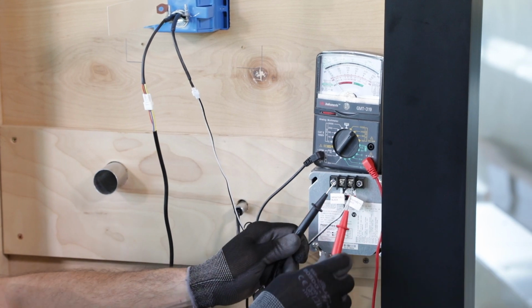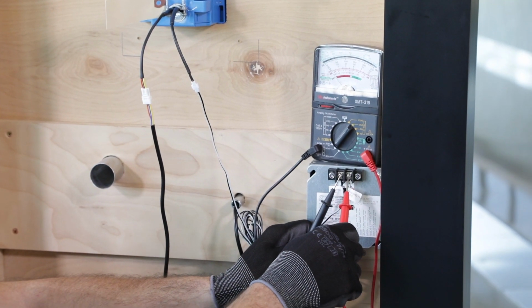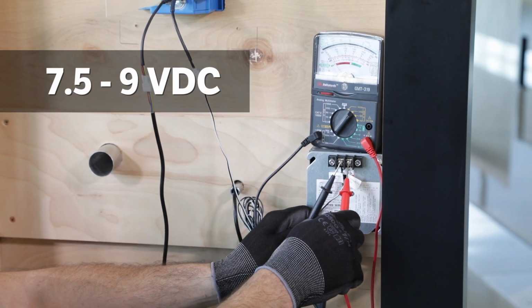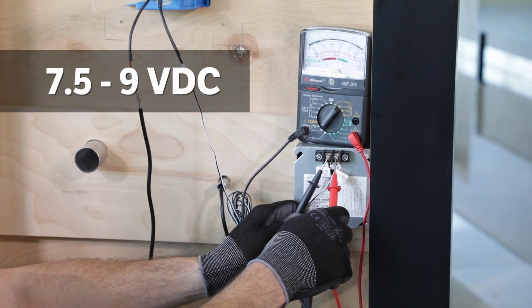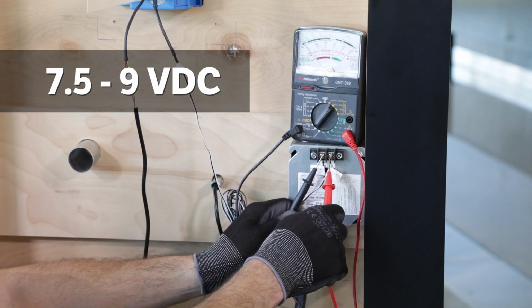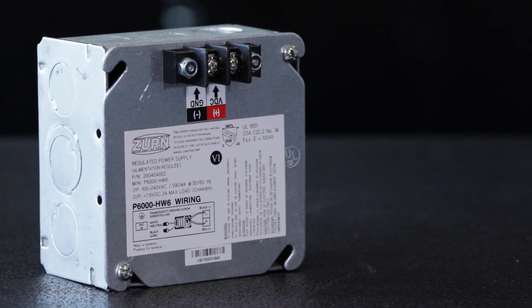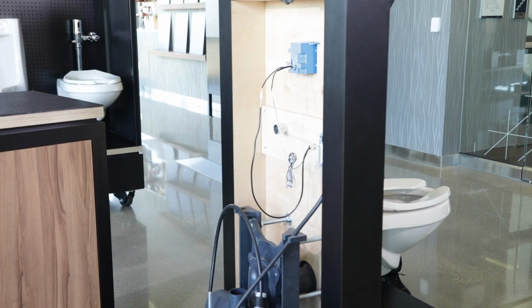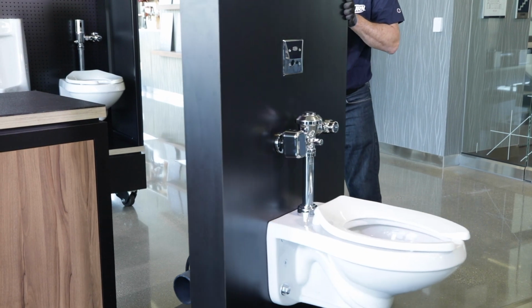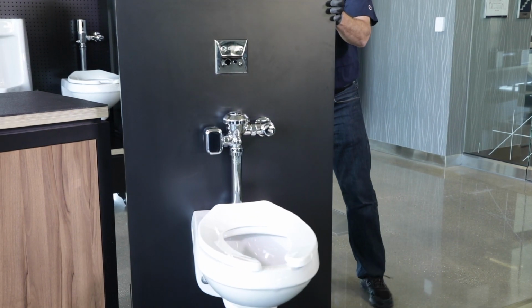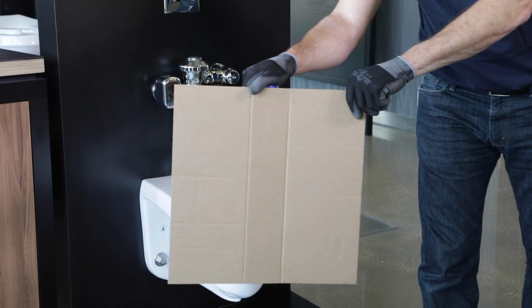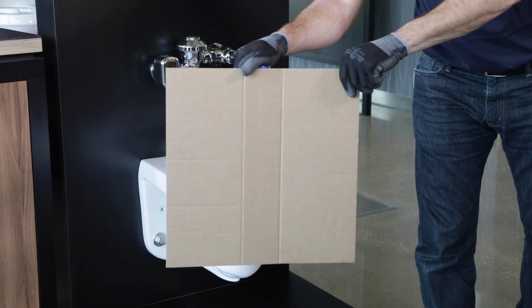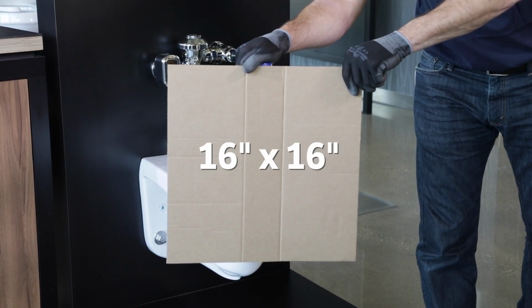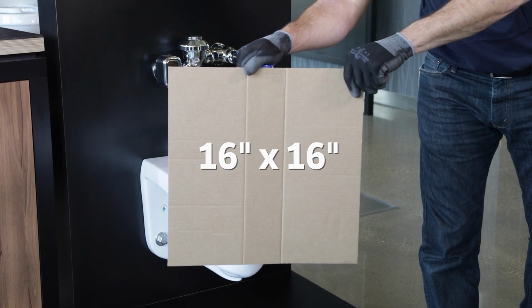Use a voltmeter to measure the voltage at the P6000 HW6 transformer. You're looking for 7.5 to 9 volts DC. If it's not within this range, schedule a professional electrician to replace the P6000 HW6. Let's say the power supply matched the voltage range. Try resetting the sensor range as your next remedy. Find a target to test the sensor. We recommend brown cardboard around 16 by 16 inches.